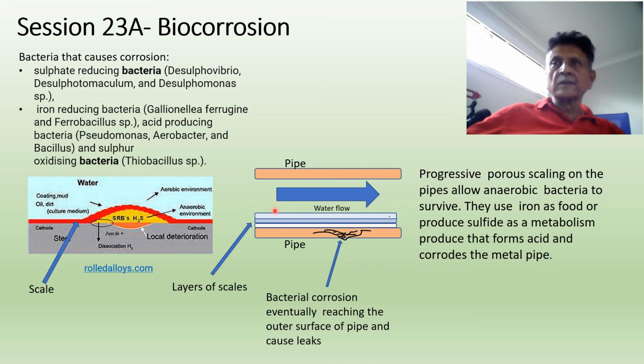Where you use chemical treatment to try to get rid of the bacteria, some of the bacteria right at the bottom may not even be exposed to the chlorine or biocide, for example, and therefore they will continue living while only the surface bacteria get killed.